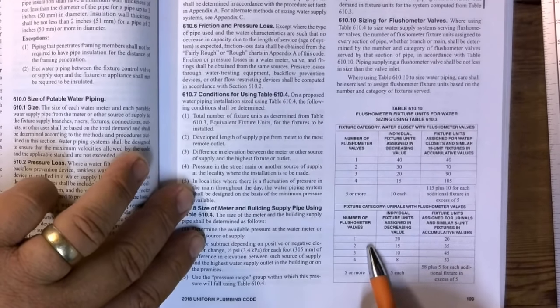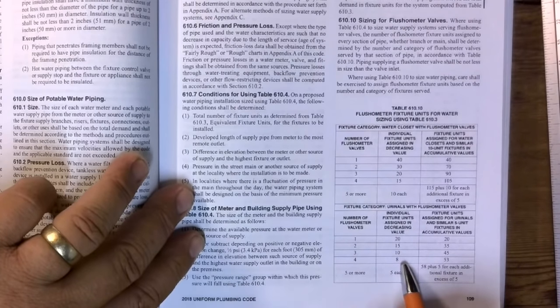Down here, this is for urinals. So one urinal is 20, two is 15, three is 10, four is eight, five or more is five each, okay? So you just end up doing the math. Two urinals is 35, right?